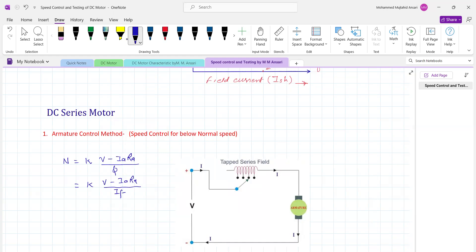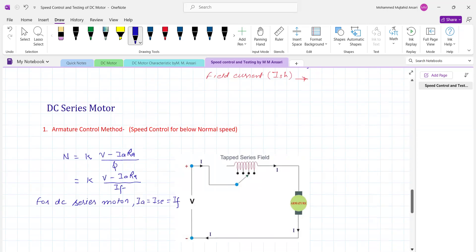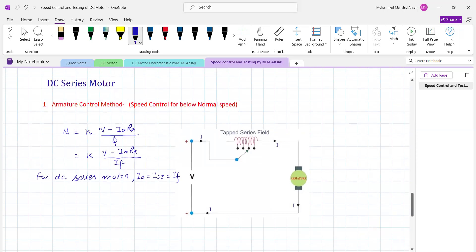For the DC series motor, to obtain speed below normal value, we provide tapping over the series field winding. By changing those taps, it is possible to obtain the speed below normal value. Similarly, for speed control using voltage across the motor — the smaller the voltage across the motor, the smaller the speed. By increasing the voltage via tap changing, the speed also increases, up to rated speed.